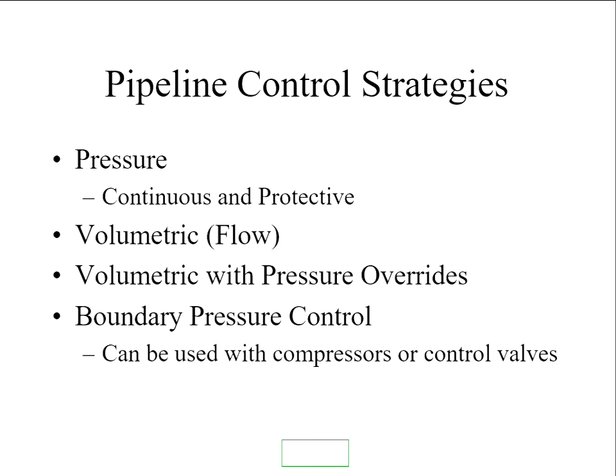And boundary pressure control is where the actual point of control, let's say for example a compressor, the pressure boundary isn't there, it's somewhere downstream, so they'll telemeter back, they'll bring back measurements and control the compressor and limit it. There are a number of those used on compressors, particularly for pipelines being uprated. So what was all 70 bar at one time, if you uprate, let's say, the first half of it to 75 bar, you want to get your 75 bar out of the compressor, but you don't want the downstream 70 bar bit to see pressure excursions. So a boundary pressure control is a form of protective system, but in principle it can be continuous.